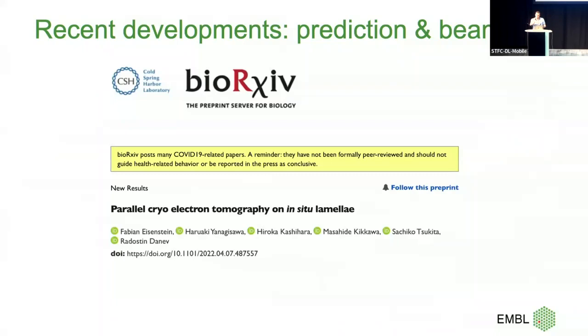Fabian Eisenstein also came up with something similar in a recent preprint: start a tilt series, set up multiple positions, with the first one as your tracking position. Once it does the tilt and takes that image, it calculates how all the other positions would move, following a rigid body rotation model. What I found very interesting is that they applied it on lamella — and with lamella you have the problem that you go into the FIB, mill them under an angle, and then put them in the TEM.